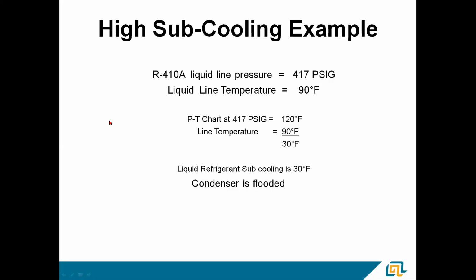High subcooling, this is what you see more often than not. You got a liquid line pressure of 417 pounds on the gauge. That converts over to a temperature of 120 degrees. We got 90 degrees of a liquid line temperature measured with our thermometer. You subtract the converted pressure to temperature from the line temperature. We find that we got 30 degrees of subcooling.